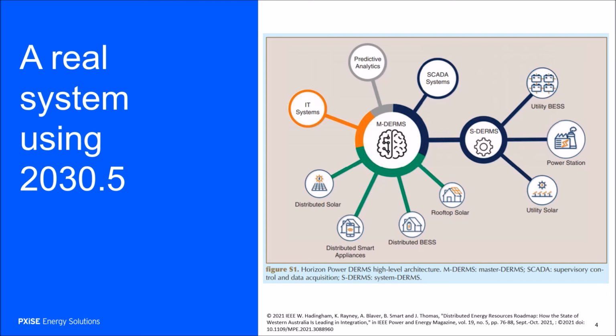I'll show you what they are in the next slide. Basically there are two methods of communicating: one is using 2030.5 to the customer DERs, and the other is using the SCADA network to communicate with the utility-controlled assets, which are controlled at a much faster rate than the customer-owned DERs.